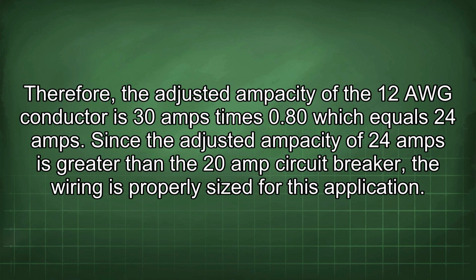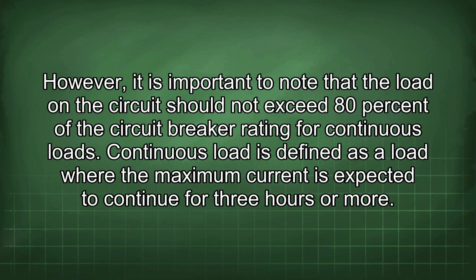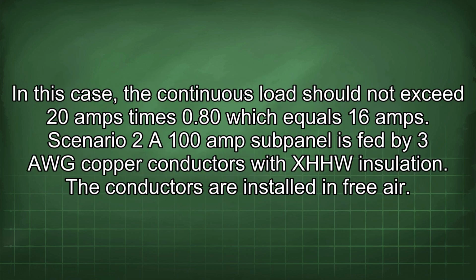for this application. However, it is important to note that the load on the circuit should not exceed 80% of the circuit breaker rating for continuous loads. Continuous load is defined as a load where the maximum current is expected to continue for 3 hours or more. In this case, the continuous load should not exceed 20 amps times 0.80, which equals 16 amps.